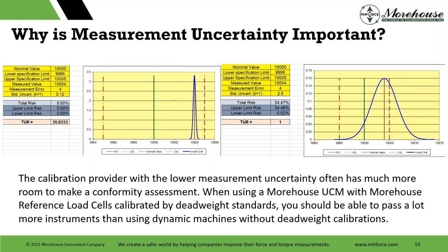You can see that this is basically showing the lower my uncertainty, the more room I have to be in tolerance. And then over here, the picture on the right is showing, hey, if I got a standard uncertainty here at 10,000 pounds of this, and I try to measure something with a specification of plus or minus 5 pounds, I'm going to have to really be on nominal to make a conformity assessment if I take into account the uncertainty of the standards.